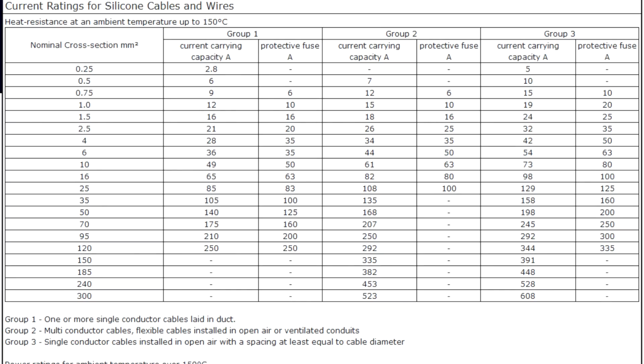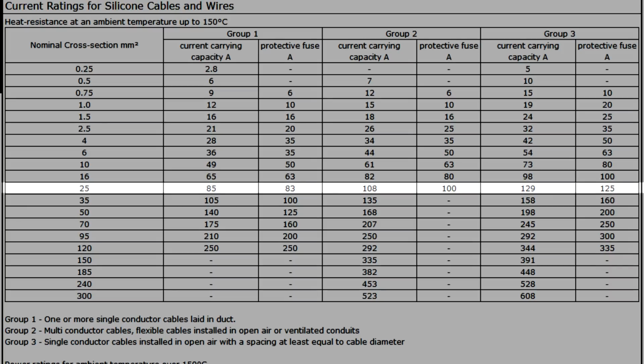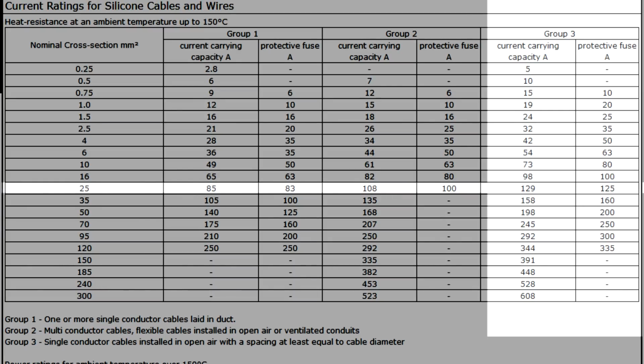And actually, if you have a look online for current carrying capacity for silicone cables, I'm using here a more conservative table because I think this is a safety issue. Let me put this on the screen. When we look at the 25 millimeter cable, under best circumstances, installed in open air, we've got a current carrying capacity of maximum 129 amps for a 25 millimeter silicone cable. This is for ambient temperatures up to 150 degrees.